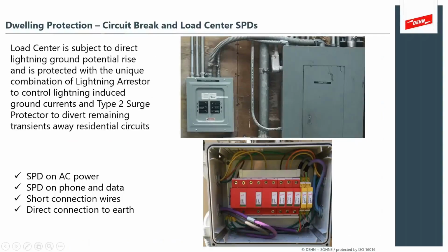What does it look like at a dwelling? So you can have any number of complicated load centers. The idea is that you want to have the surge protection as close as possible to the main bus to do the most good for the dwelling. So in this case, what you're looking for is to have the surge protection directly on the AC power feed. You want to make sure you're paying attention to the ratings of the devices so that you can advise if they need fuses for disconnects, or very often our products do not need fuses to be installed on such load centers. You want short connection wires, you want a direct connection to the earthing system.